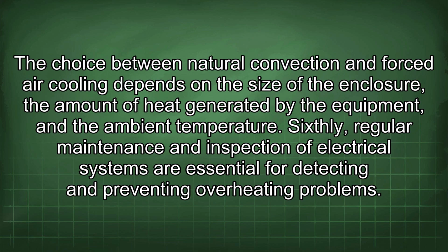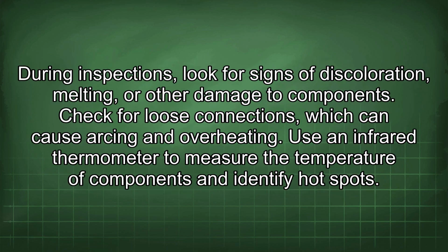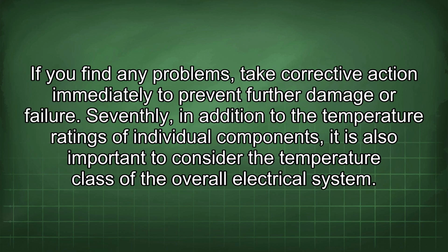Sixthly, regular maintenance and inspection of electrical systems are essential for detecting and preventing overheating problems. During inspections, look for signs of discoloration, melting, or other damage to components. Check for loose connections, which can cause arcing and overheating. Use an infrared thermometer to measure the temperature of components and identify hotspots. If you find any problems, take corrective action immediately to prevent further damage or failure.